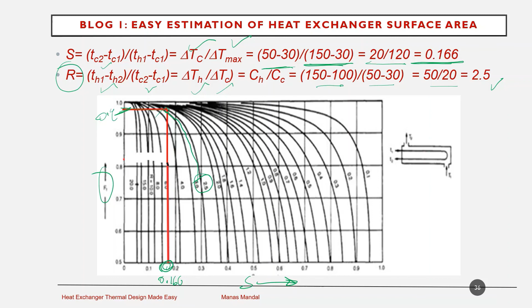Similarly, we can calculate R and then plot the R. R is nothing but delta TH divided by delta TC, the differential of the hot fluid divided by the differential of the cold fluid. 150 minus 100 divided by 50 minus 30 gives us 2.5. So this is the 2.5 R curve. Now we have to go upwards and cut this R at some point and then go parallel to the x-axis to cut F. This is 0.98. Putting the value of 0.98 in the equation F into LMTD gives us 82.4 degrees C.